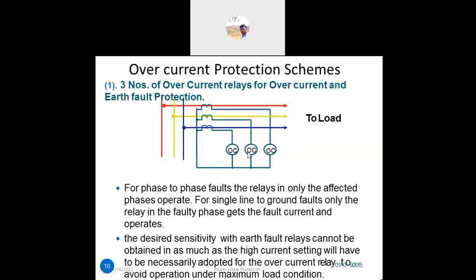In the overcurrent protection scheme, three relays are placed — one for each phase. For an LG fault, only the affected phase relay will operate. For an LL fault, only the affected phases will operate. The desired sensitivity with earth fault relays cannot be obtained because a high current setting must necessarily be adopted for overcurrent protection.